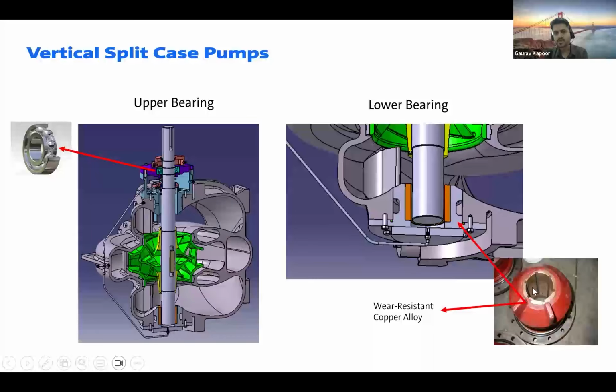It is also why we need to have this sleeve bearing instead of a roller bearing, because the complete weight of the water and the accessories lies on this bottom bearing. So if it is a ball bearing, there are very high chances of failure, and this becomes a very weak point for failure. So that's why, if you're going for a vertical split case pump because of space constraints, you should always make sure that it's a pure vertical split case design with a sleeve bearing on the non-drive end. This is a very, very important point to understand.